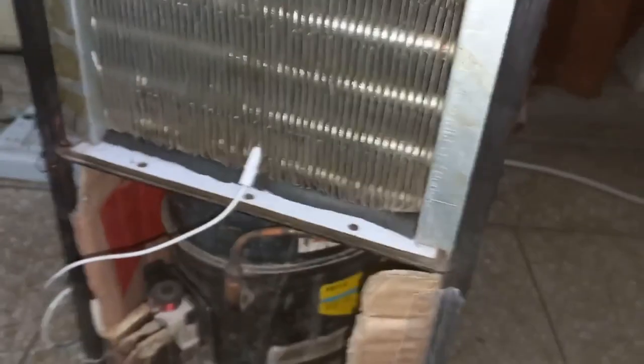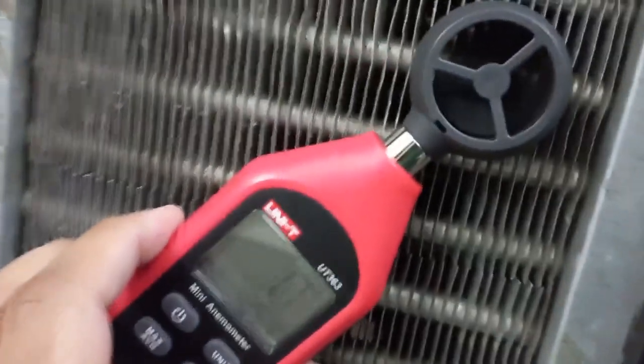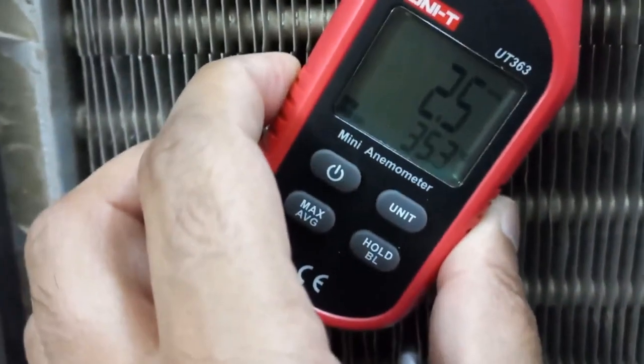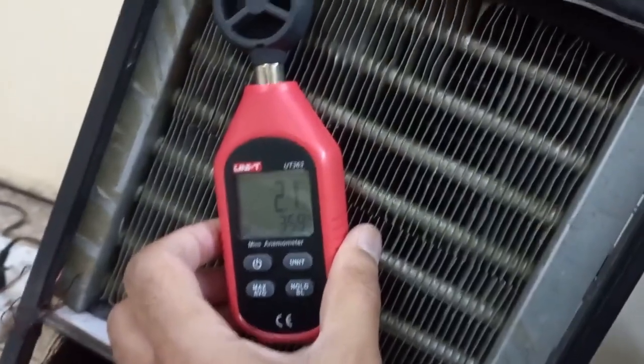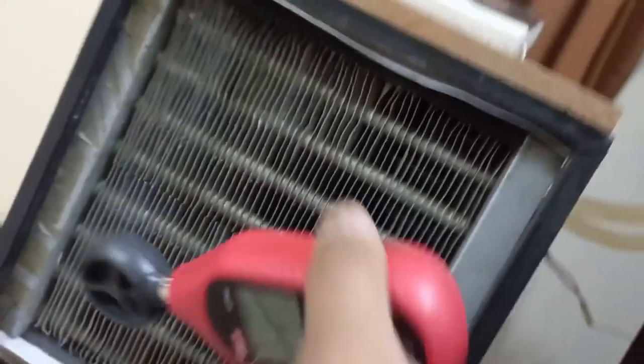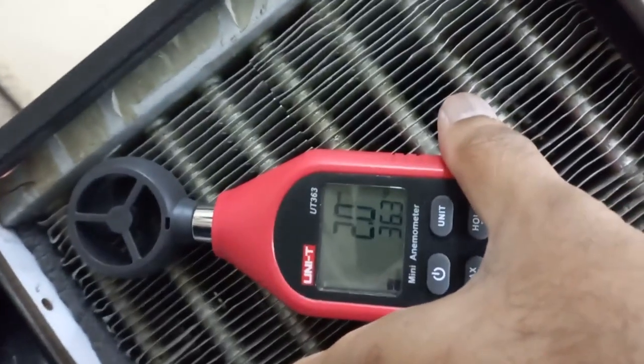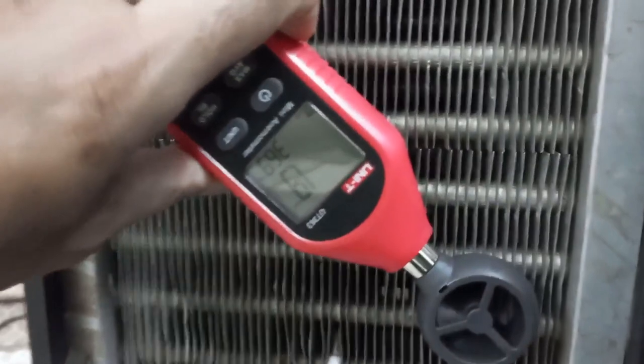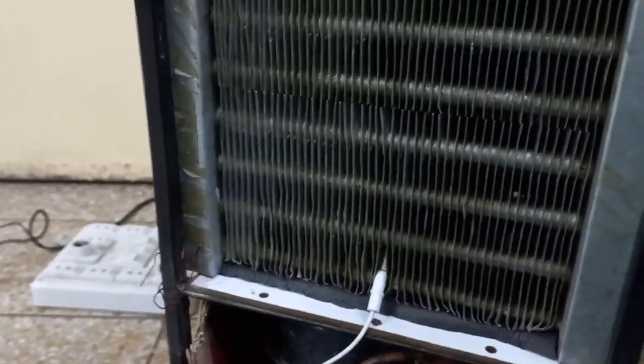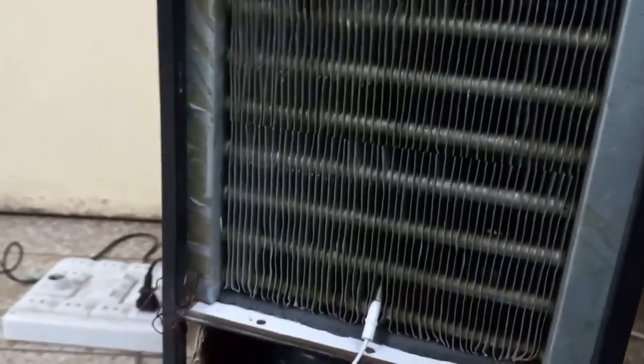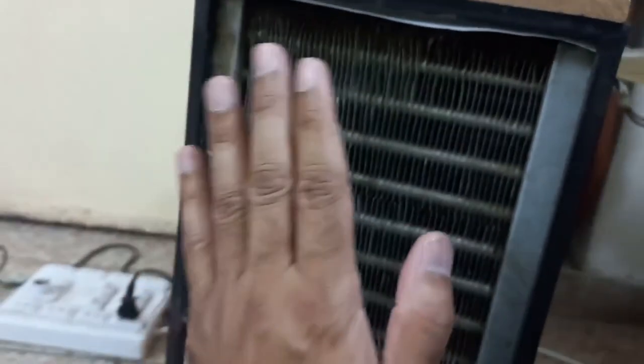Now if I check air velocity, meter is at 0. Now if I put it at this corner, it's 2.0 or 2.5. At this corner, 2.1, 2.2, and downside this corner, 2.1, 2.0, and at this corner also 1.9 or 2.0. Before it was 1.3 meter per second, and now it's 2.0 meter per second, and I also feel the air on my hand, it's coming too much.